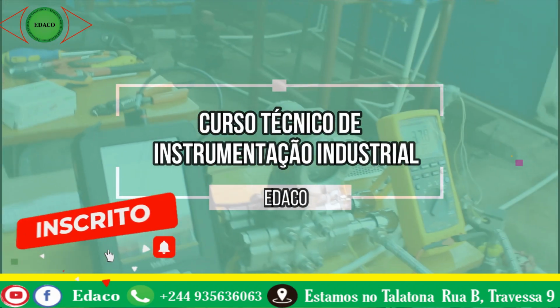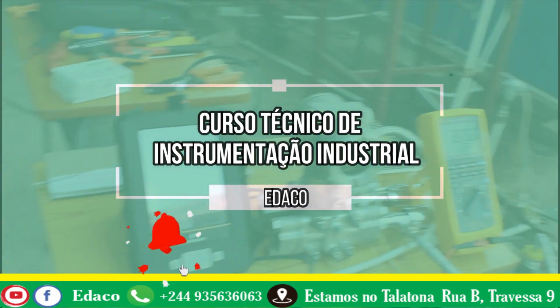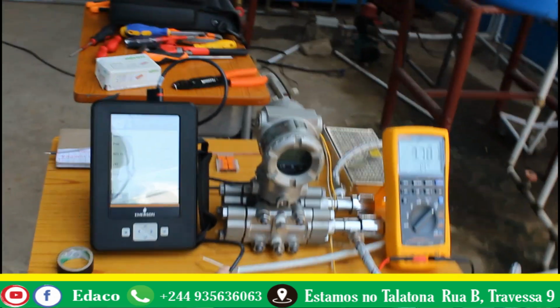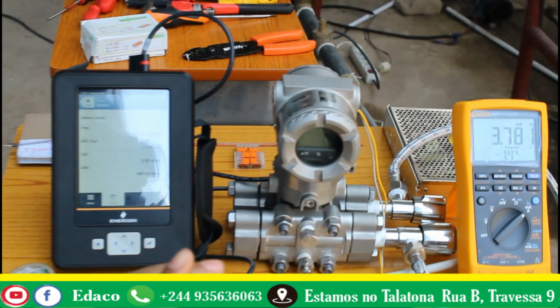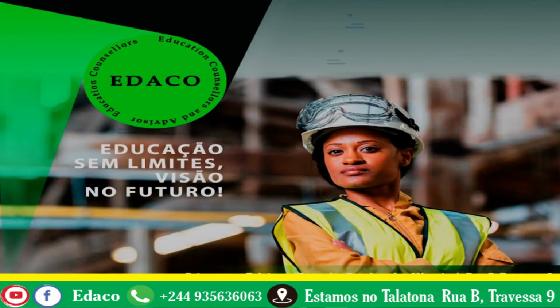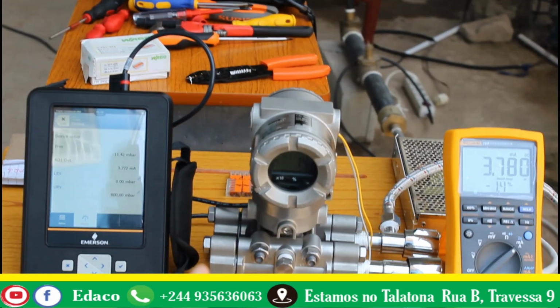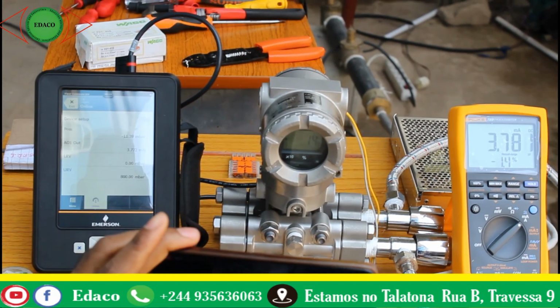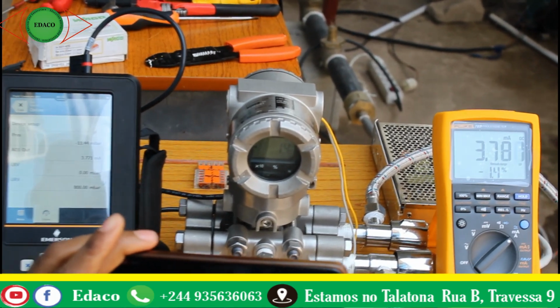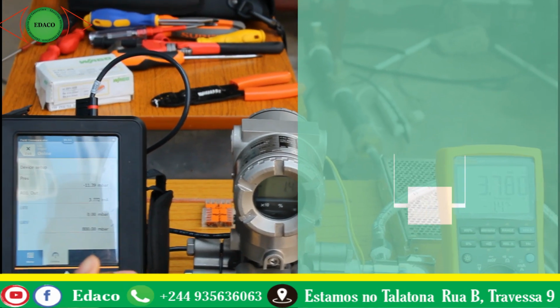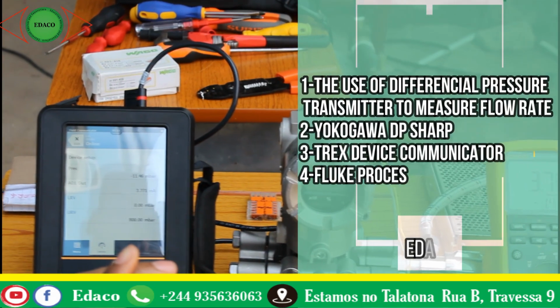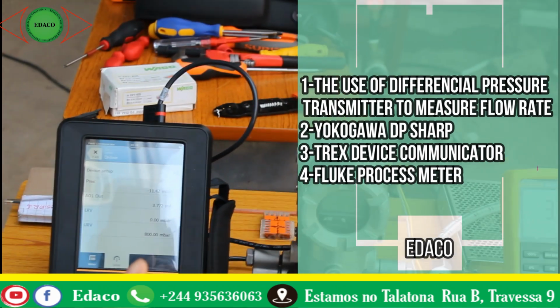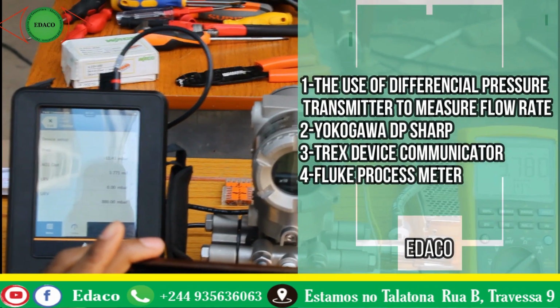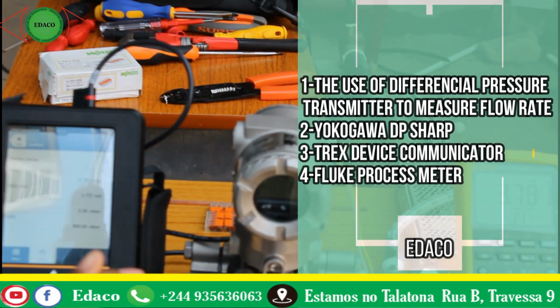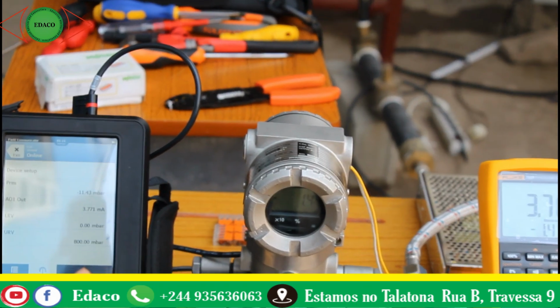All right, so as I was saying, differential pressure transmitters can be used to measure flow rate, and they can also be used to measure level through the hydrostatic pressure. Hydrostatic pressure is the density of the fluid times the gravity times the height, and the height in this equation is the level.